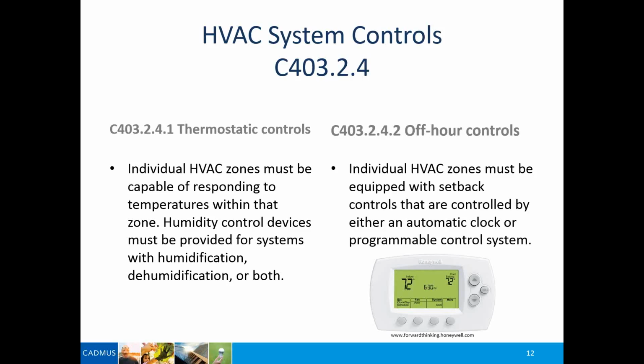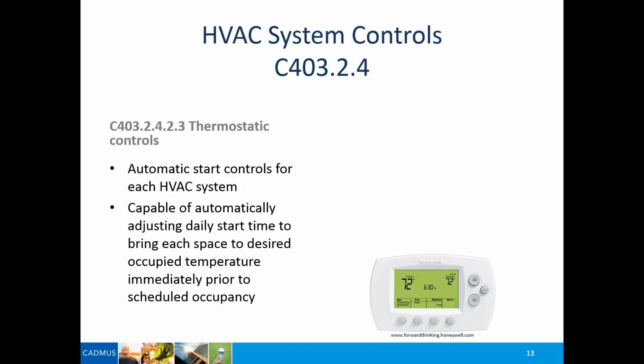And then if you downloaded the presentation before this, I've added a slide because I thought we should also talk about the requirement for an optimum start control. Essentially, most systems right now are designed to come on at the same time every day to get the system basically down to temperature. So if your occupancy is at 8 in the morning, and let's say you have your system designed to come on at 6 o'clock every morning to cool the temperature before the first occupant comes in, what this control will essentially do is look at the outside weather conditions, look at the interior temperatures, and optimize that start time. So maybe it only has to start an hour prior to occupancy to get it down to the temperature you want for the occupant. So if I can actually reduce my startup time, I'm going to be saving quite a bit of energy from that standpoint. So it's a new requirement again in the code, the optimum start.